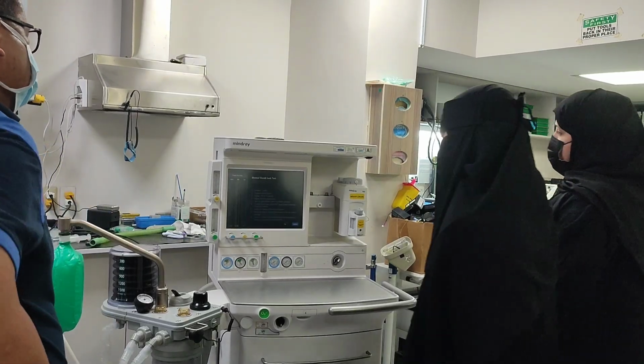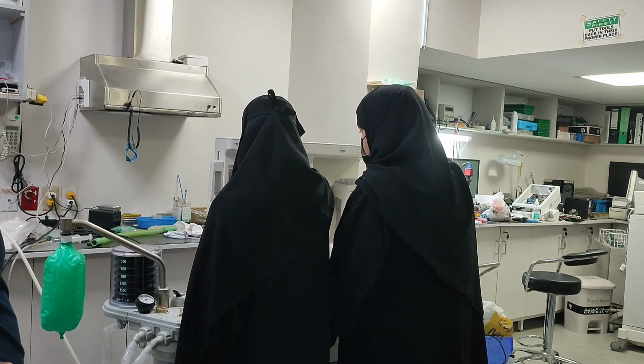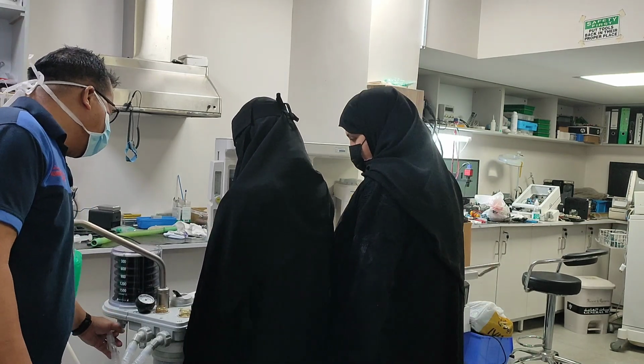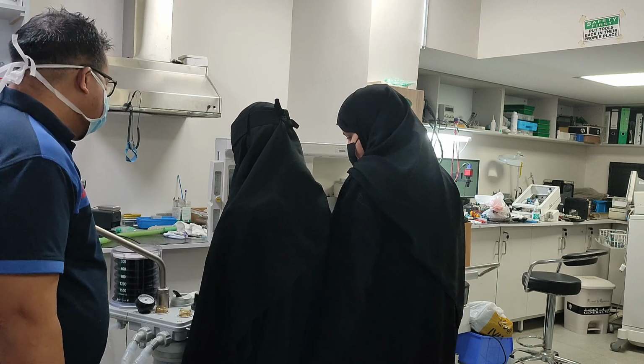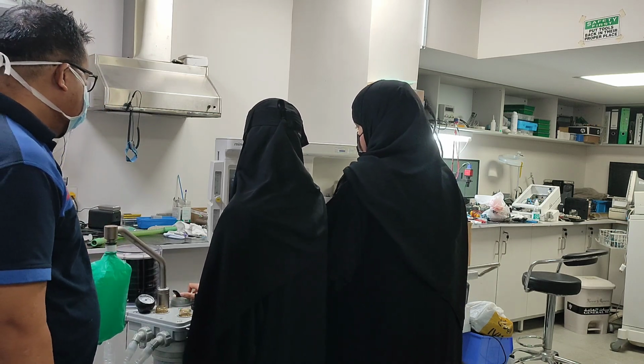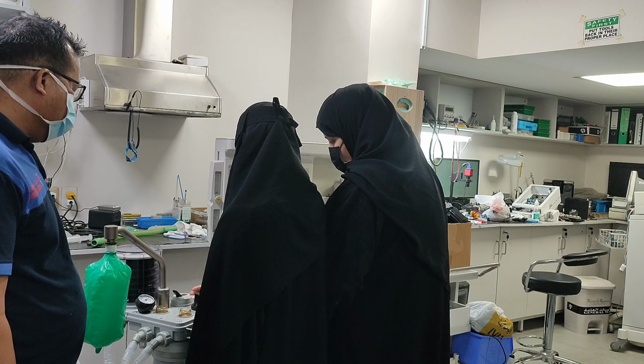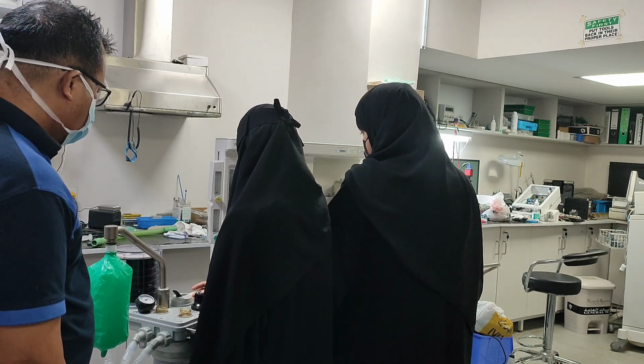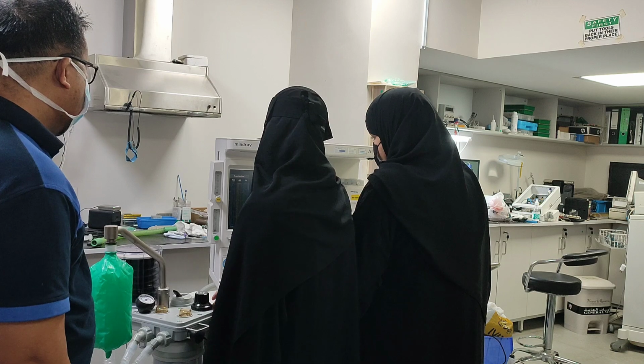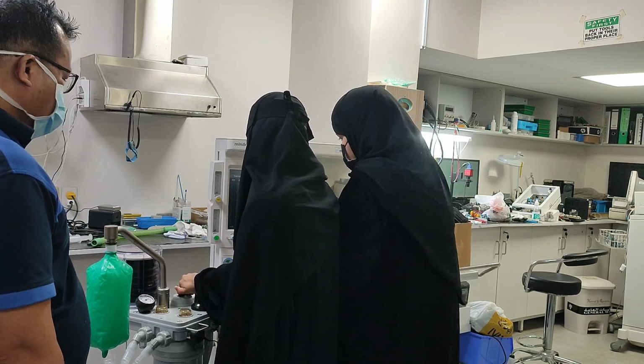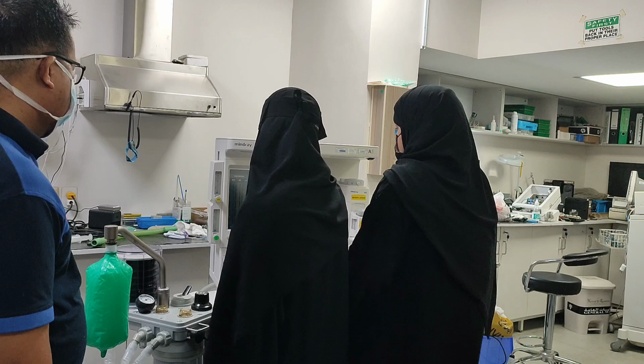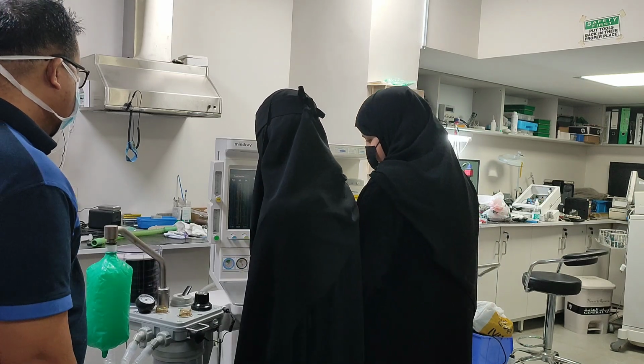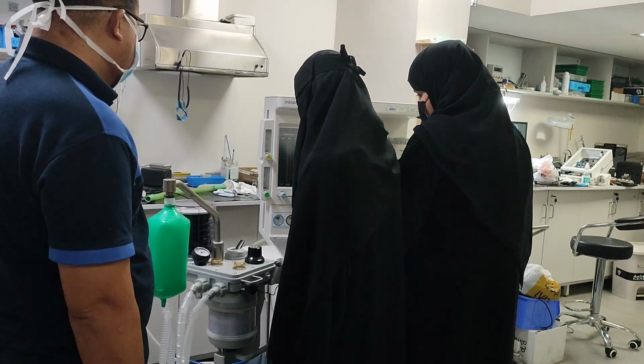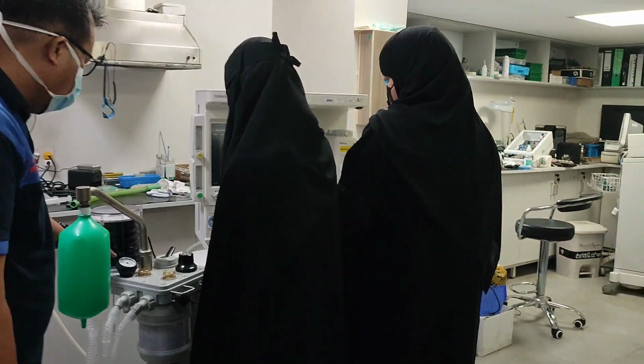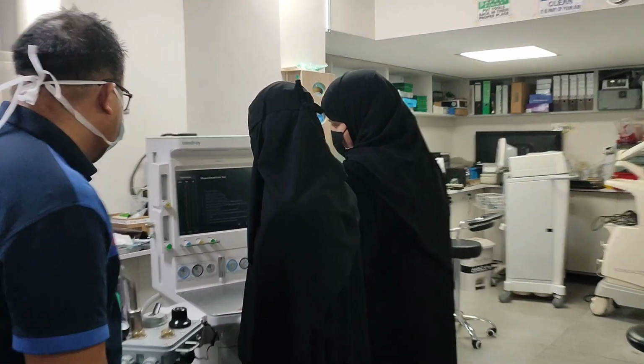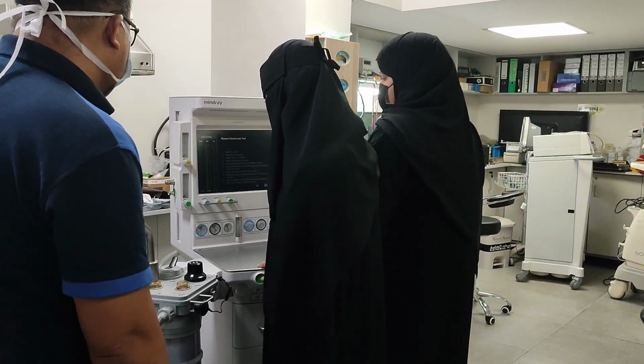The manual circuit test. First we just seal the white piece. Okay, seal. Next, install the manual one, already installed. Adjust APL to 75. Then adjust all flow meters to 0. All flow meters, yes, this is the flow meter, all 0. Set the auto manual to manual and push until between 25 and 35. Put it in the 30.